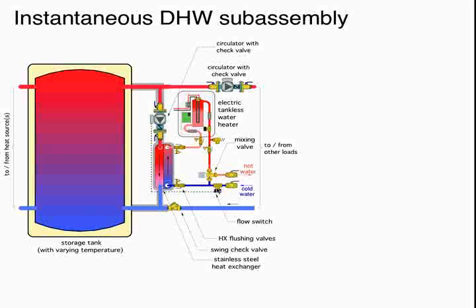We open a faucet, we get hot water demand, cold water flows in past our flow switch. The flow switches typically will close at around 0.6 of a gallon per minute. And through a relay, we're going to turn this circulator on. It is important to keep this assembly close to the tank. We don't want to have a lot of piping between the tank and this, because that's going to delay transfer of heat from the tank to the heat exchanger.